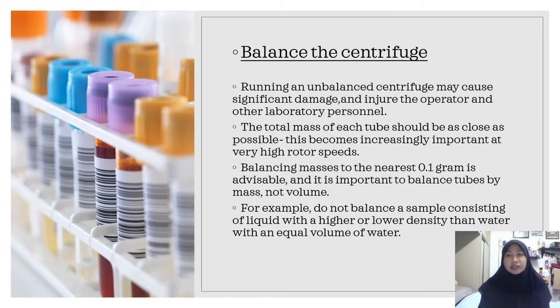Balancing the centrifuge is needed, where running an unbalanced centrifuge may cause significant damage and injure the operator and other lab personnel. The total mass of each tube should be as close as possible, which becomes increasingly important at very high rotor speeds.